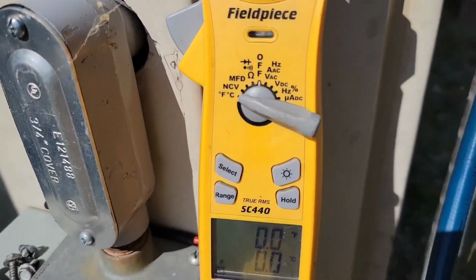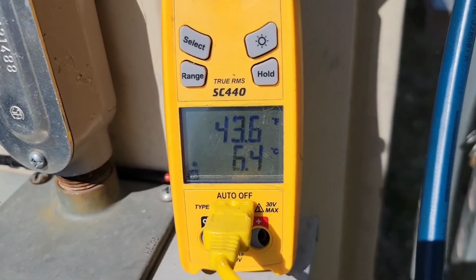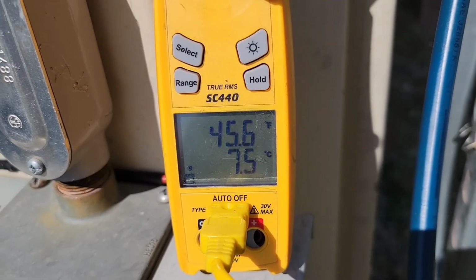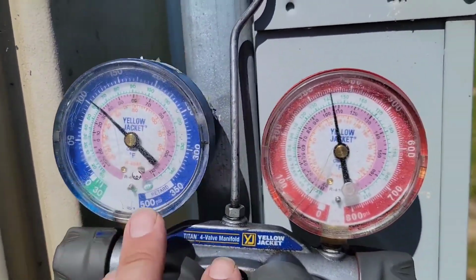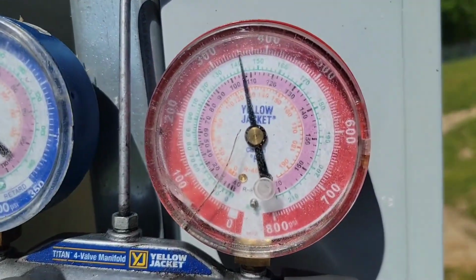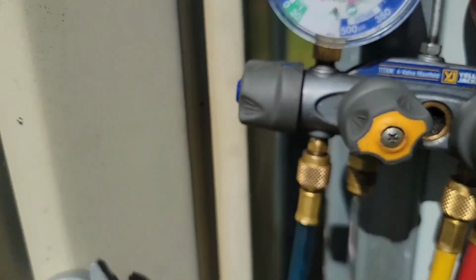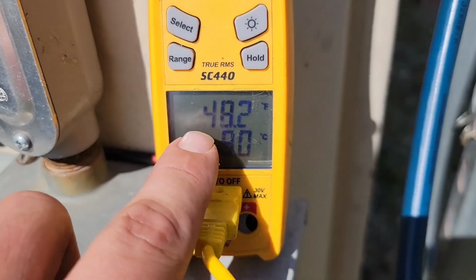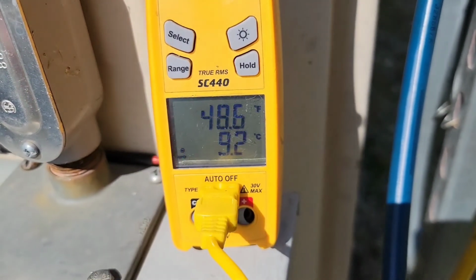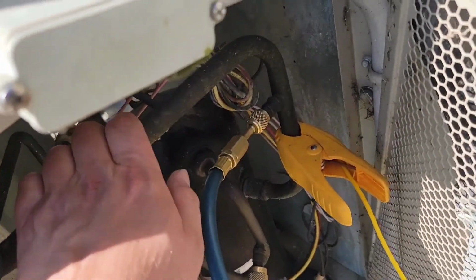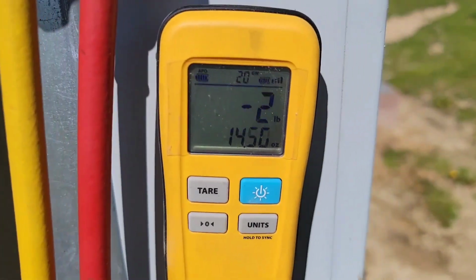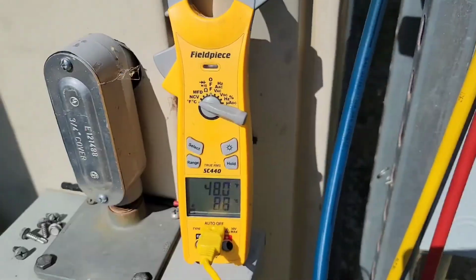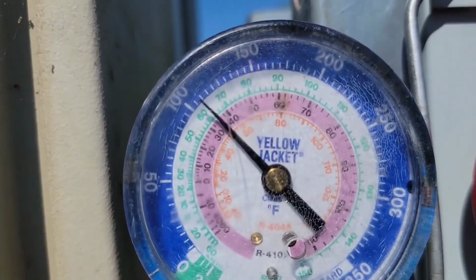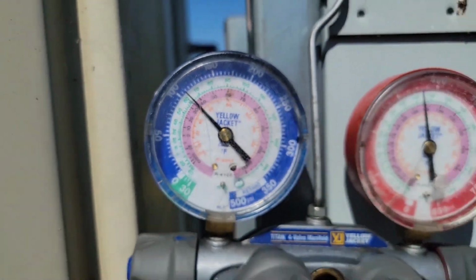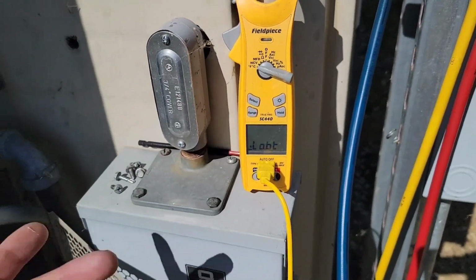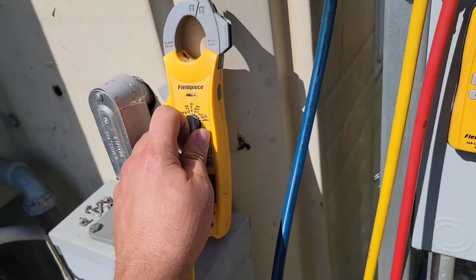So let me turn this back on. I gotta replace the battery in this thing. So 45, so we got a good superheat. I'm gonna say this unit is pretty well charged. 350 on the head, 105 on the suction, 48 on the suction line temperature. We've added almost 3 pounds, and 48 and about 35, that's about 12 degrees of superheat. So our superheat's pretty good. It's jumping around right now.